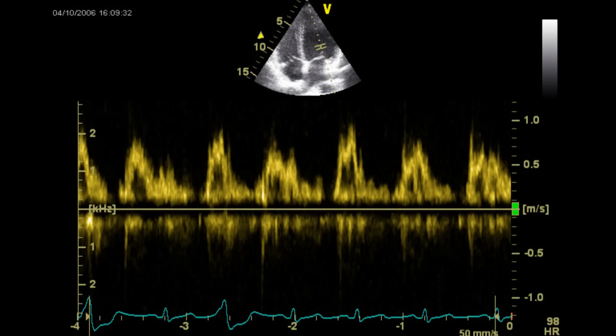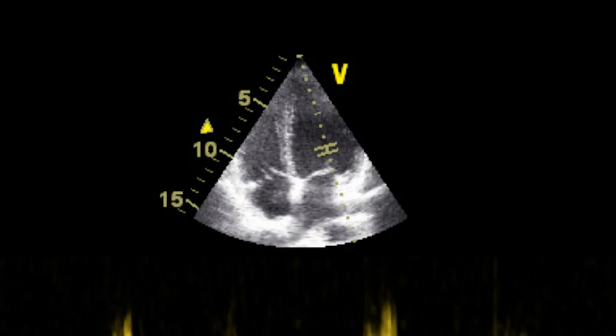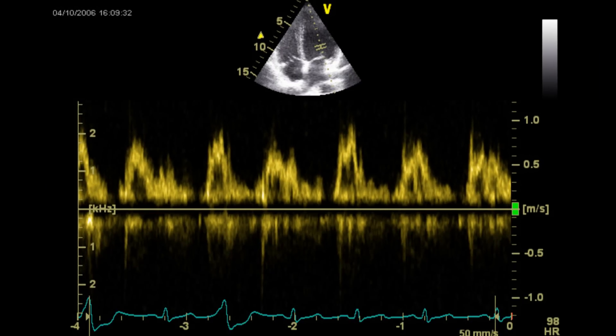That's why doctors will usually use a conventional ultrasound device that also displays a nice image to go with it, and also uses a different type of Doppler — a gated Doppler — so they can measure the blood flow in just a very specific area. For example, as shown here, right next to the valve in the heart, and what you can see just below that image is the actual Doppler signal.